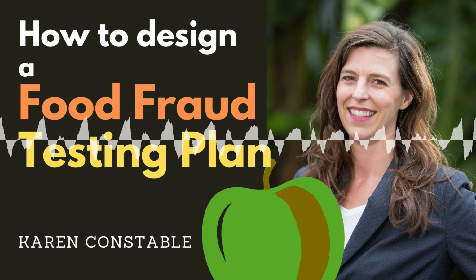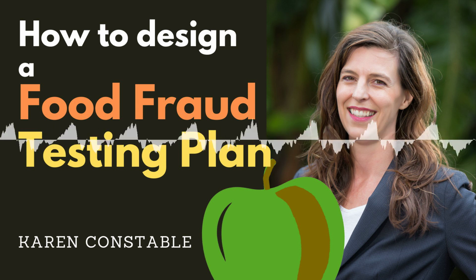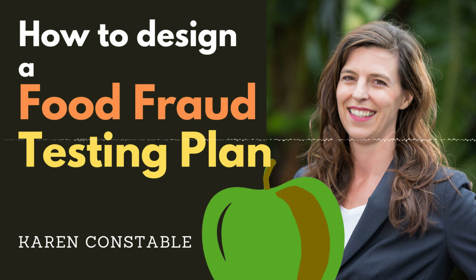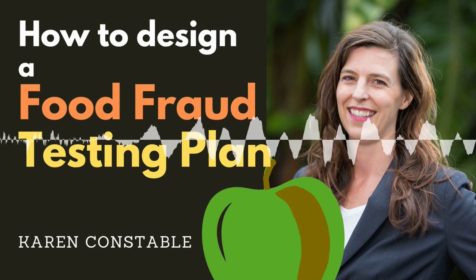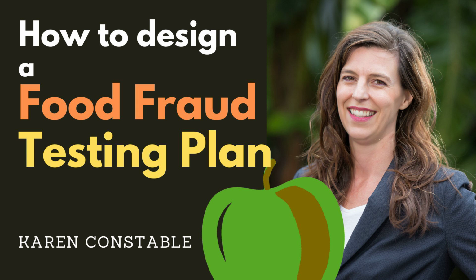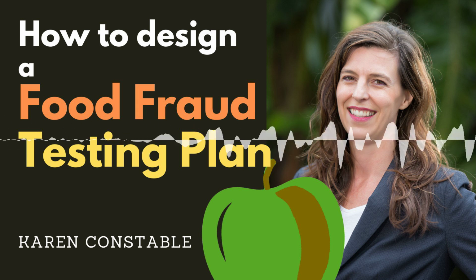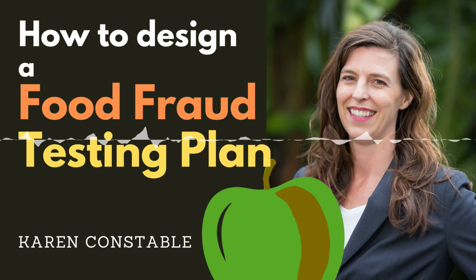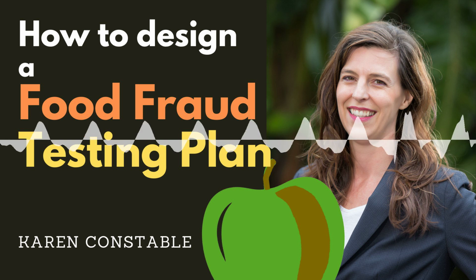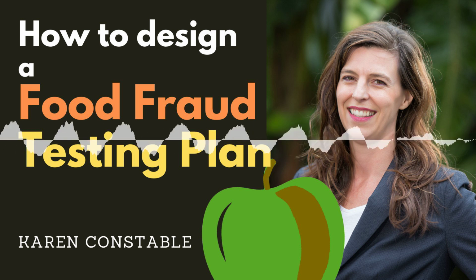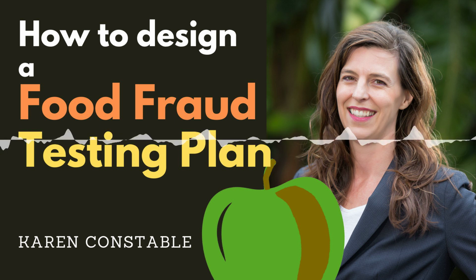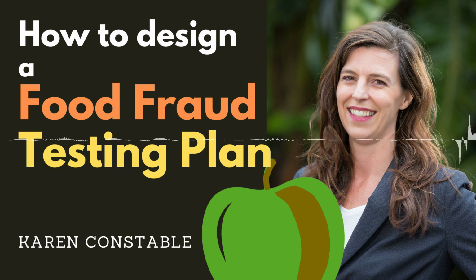Precision is a measure of the ability to reproduce an answer between determinations using the same equipment and the same experimental approach. And so that is different to accuracy, which is a measure of how close one can actually measure the true value of the parameter being measured. That's also different from reproducibility, which is a measure of the ability to reproduce an answer by using the same experimental approach, but in different laboratories and using different equipment.